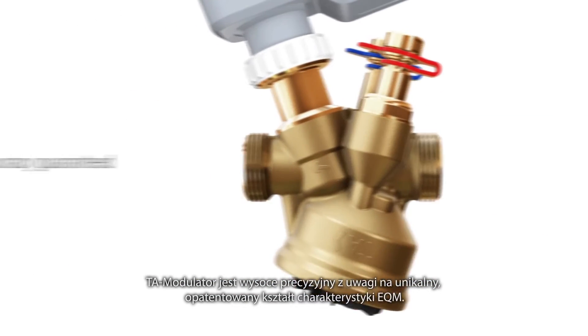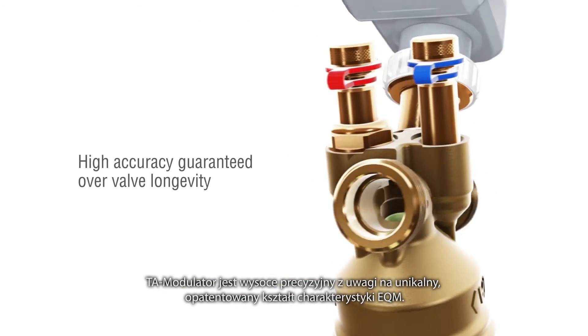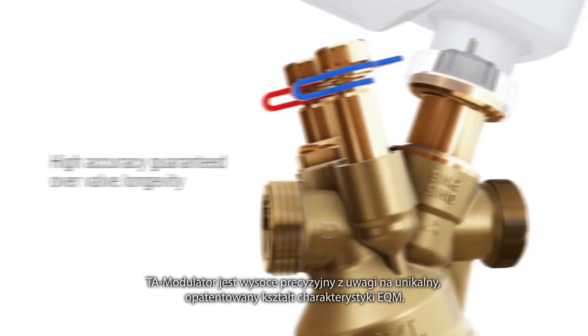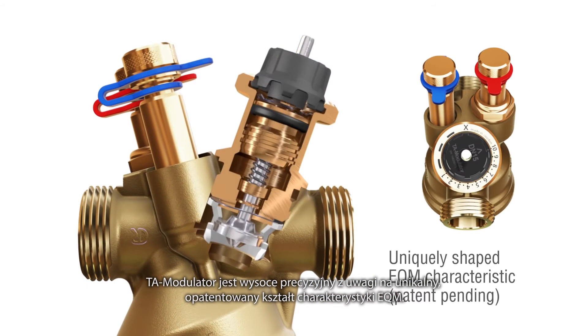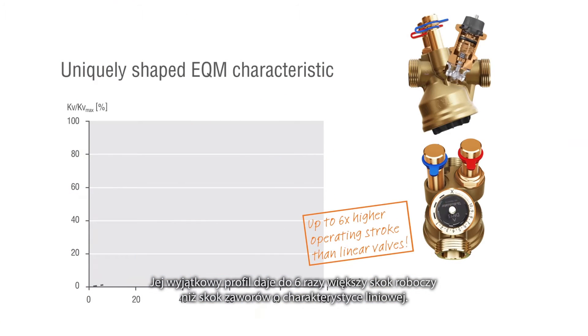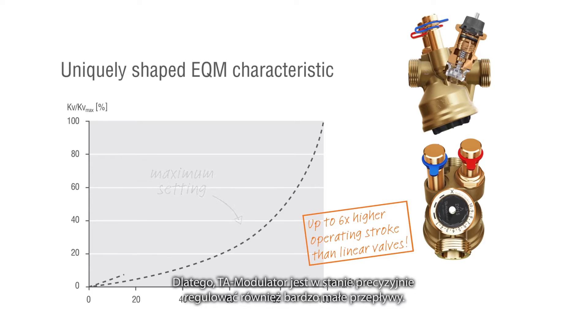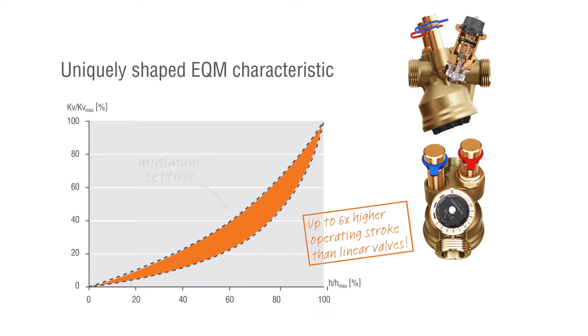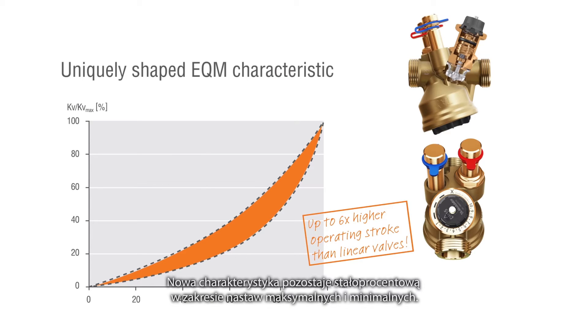The new highly precise TA Modulator is unique due to its new patent-pending uniquely shaped EQM characteristic. Its uniquely shaped profile provides an up to 6 times higher operating stroke than linear valves. Therefore, TA Modulator is able to precisely control also very small flows. The new characteristic remains equal percentage within the range of maximum and minimum flow settings.